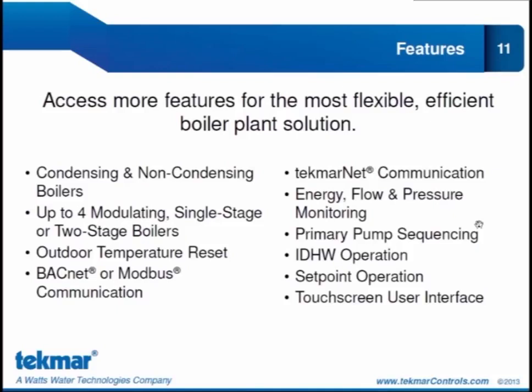features the same things that are common to the 274 and 275, such as warm weather shutdown, automatic differential, domestic hot water priority, equal runtime rotation and pump exercising, pump post-purge, and the fixed lead, fixed last operation that you're familiar with. Because we're also controlling modulating boilers, we can set up the modulating mode as sequential or parallel as well. We're not going to go into these today because you're already familiar with the operation of these features.